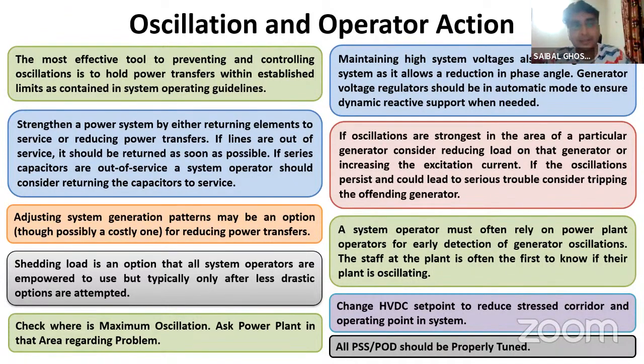Some actions cannot be taken in real time, like PSS tuning - you cannot do that in real time. You have to do it with the help of the OEM, and it needs a lot of studies, so that is in offline mode. In real time, if the operator can identify it is a forced oscillation coming from malfunctioning of the governor from a unit, then it will switch off that unit. If it is coming from malfunction of an HVDC, it can switch off that HVDC. And if it is seen that it is because of inter-area oscillation due to high loading in the AC corridor, then the operator can modulate HVDC power to relieve the AC corridor power.